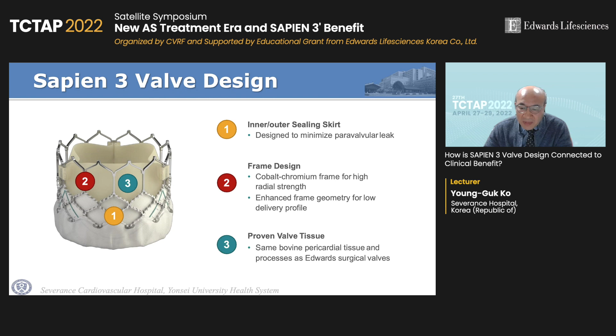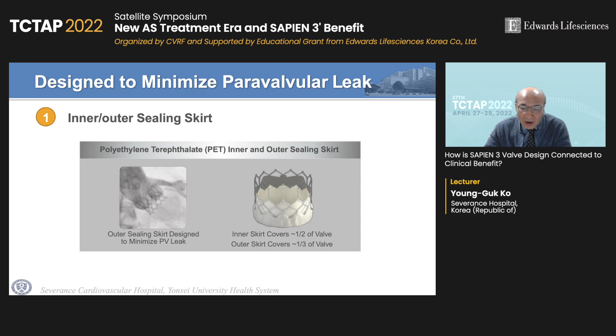As you will all know, SAPIEN 3 is a balloon-expandable valve characterized by an inner and outer sealing skirt, a cobalt-chromium frame with strong radial strength, and bovine pericardial tissue, which is the same material used for advanced surgical valves. The SAPIEN valve is designed to reduce paravalvular leak. It has inner and outer sealing skirts made of polyethylene terephthalate polymer; the inner skirt covers 1/2 of the valve frame, and the outer skirt covers 1/3 of the frame.